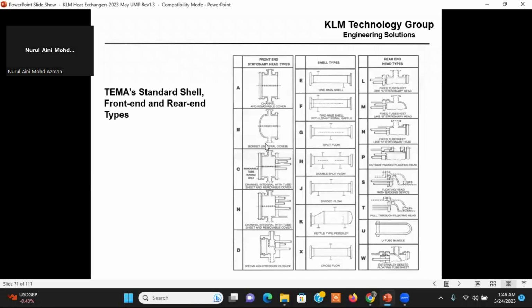So we have A, B, C, N. We've got these, and we've got these. All right, so typically, I'm going to use a B, E, and an M for hydrocarbon service. So that's going to be my choice. Okay. For cooling water, I might use an A. For high pressure, I'm going to use down here. If I've got a kettle reboiler, I'm obviously going to use K.